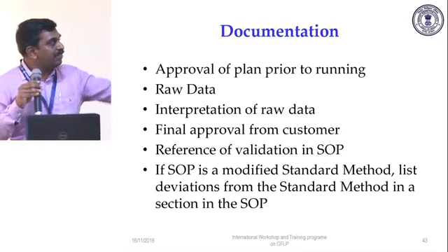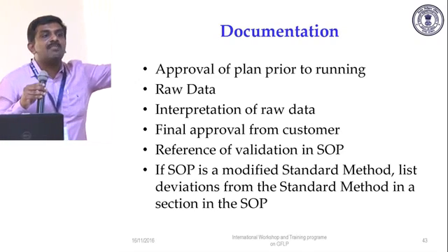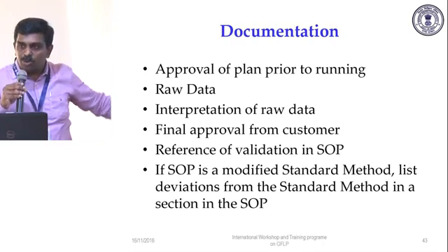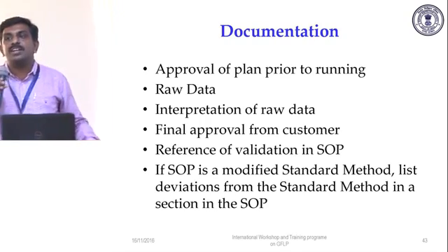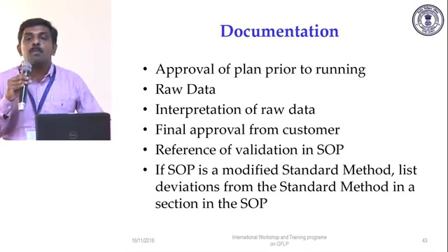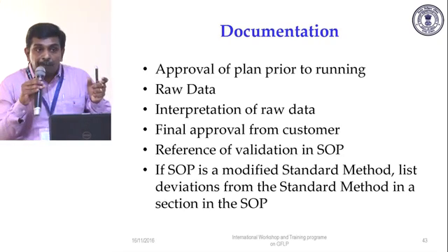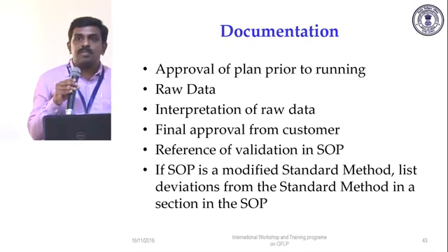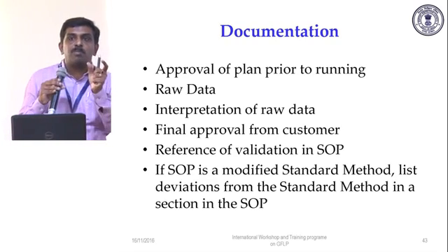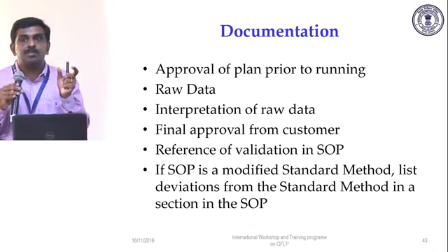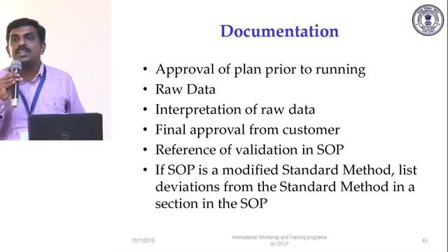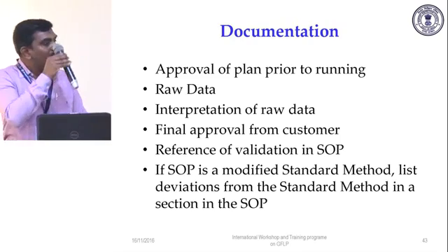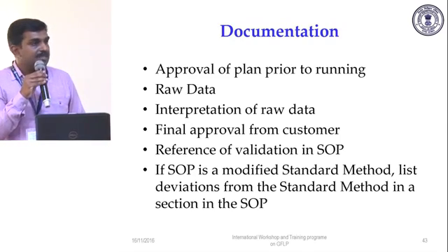See, validation, we have discussed so many things. You need to have acceptance criteria for all this. You may be validating against a protocol, so you should have defined criteria. And you should properly report it. You have to properly make a report. I think ISO IEC 17025 is catching on to it, that you should properly report it and make a statement that this method is fit for intended purpose. You should conclude that your method, after doing all this, is fit for purpose.